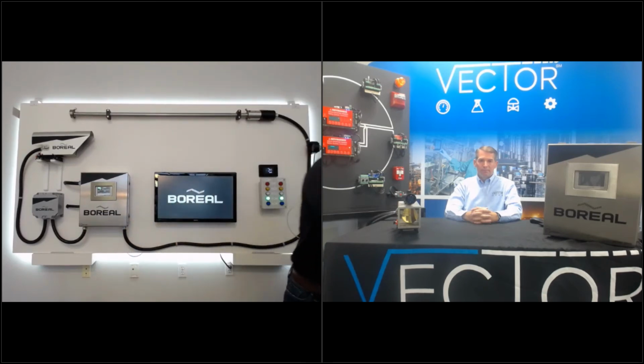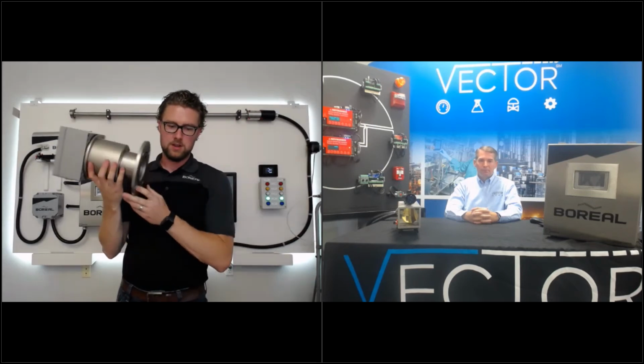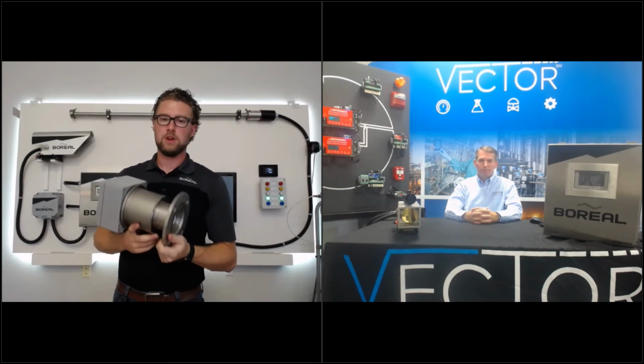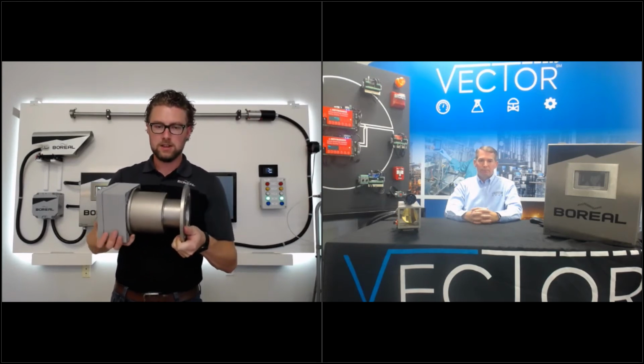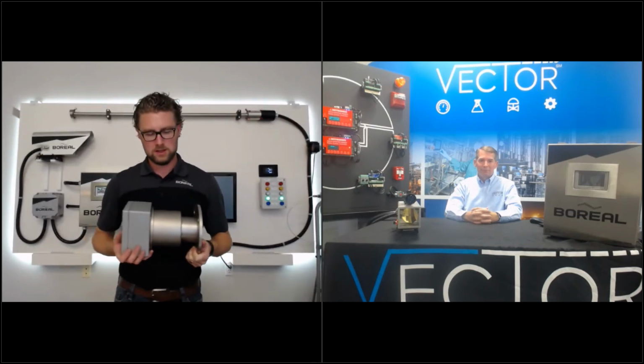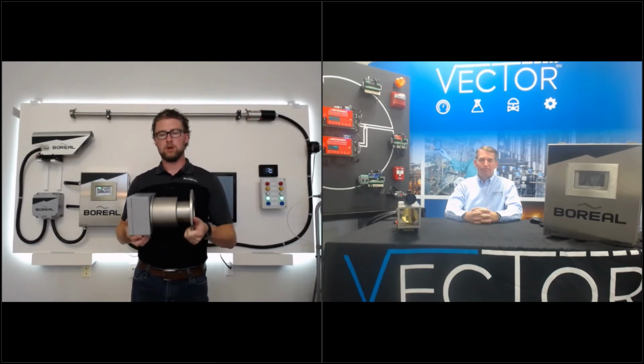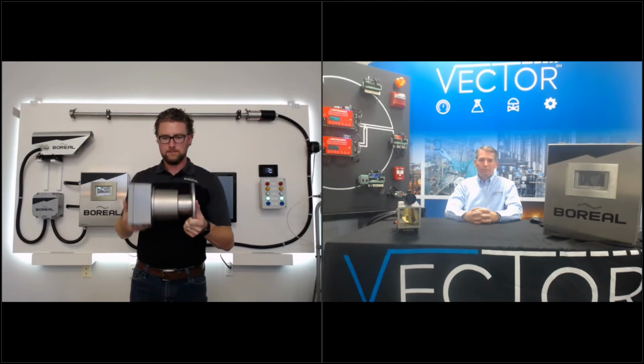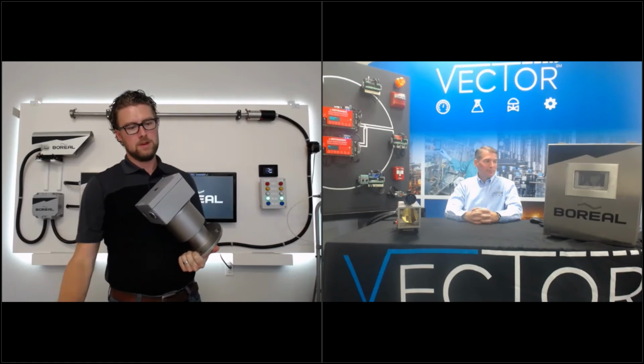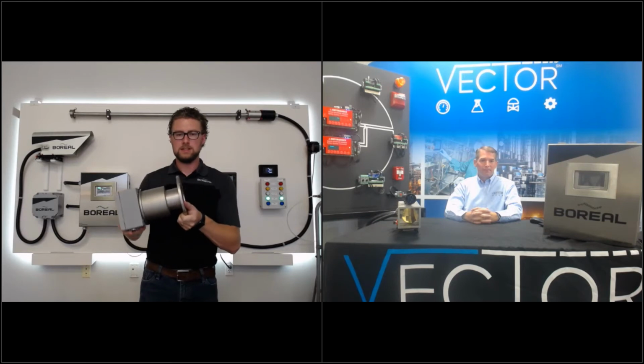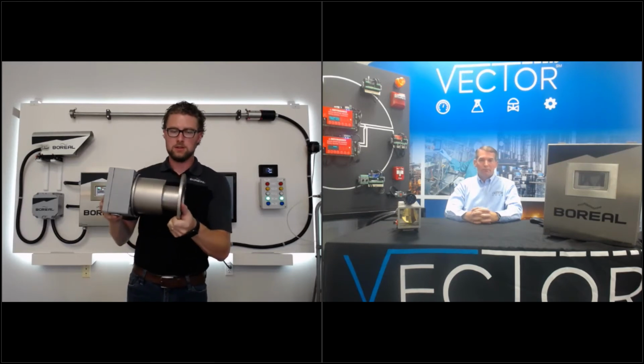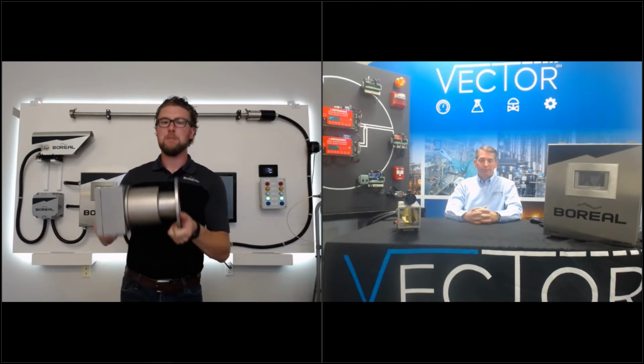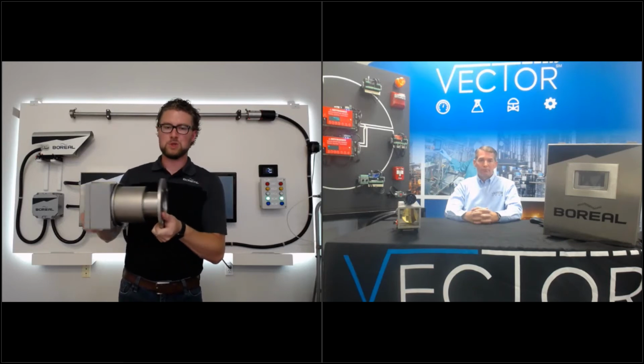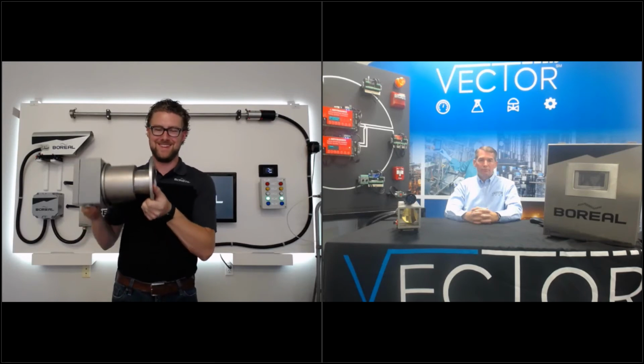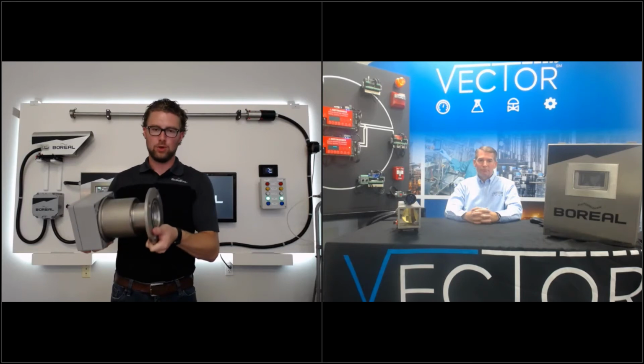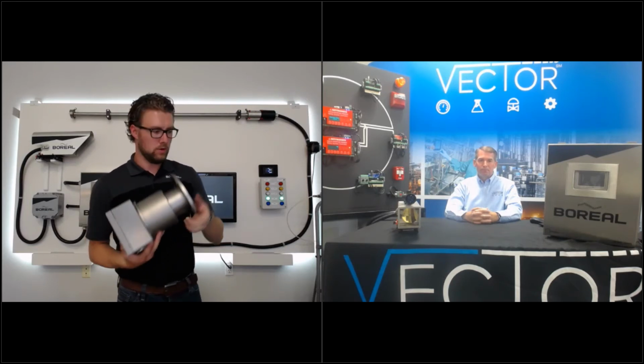We also have stack and duct probe arrangements as well. This is another really handy tool to make in situ direct and non-contact measurements. As the name suggests, the stack or duct, that seems pretty obvious, but a really good application for this product is for API 751 safe haven monitoring applications, where you mount this to the inlet duct of your HVAC system. From there, you can detect the presence of toxic or combustible gases the second it enters your HVAC system, rather than waiting 10, 30, 60 seconds for your system to respond to that target gas. This helps prevent gassing and poisoning of individuals working within a control room next to the process unit or process area as well.